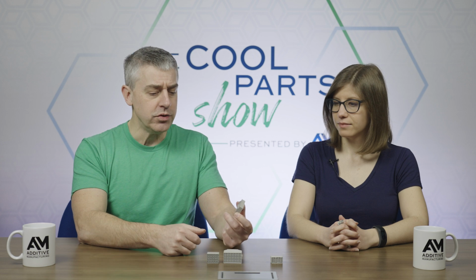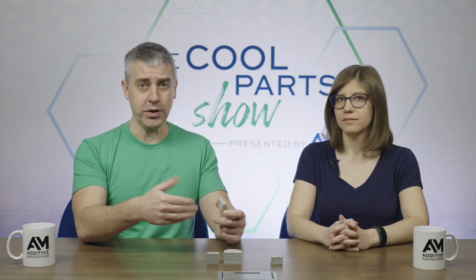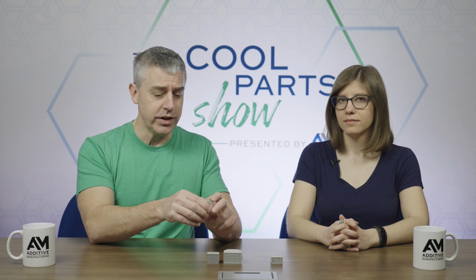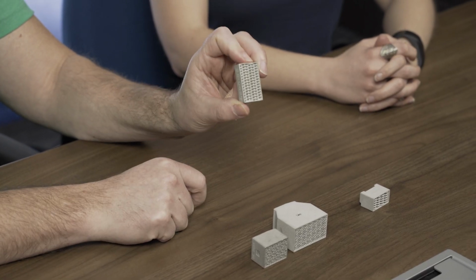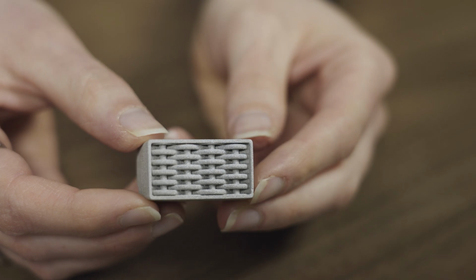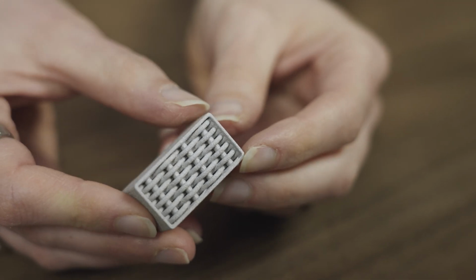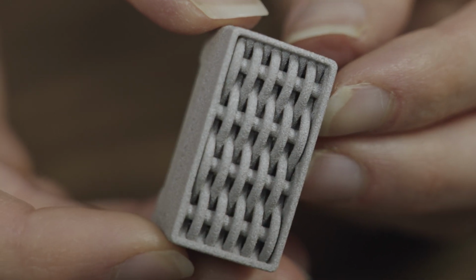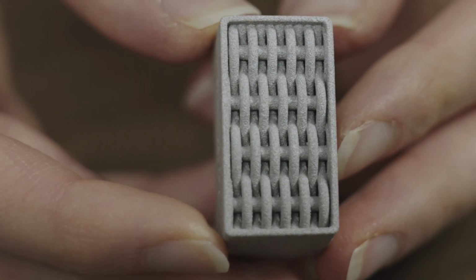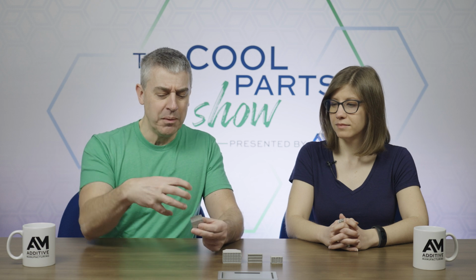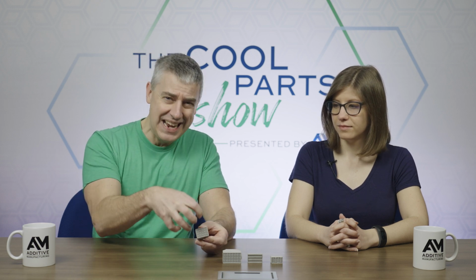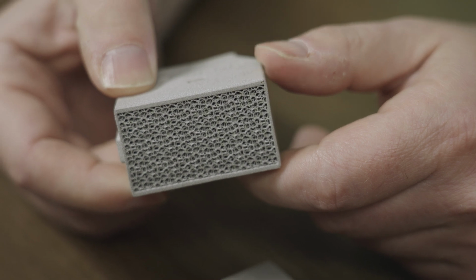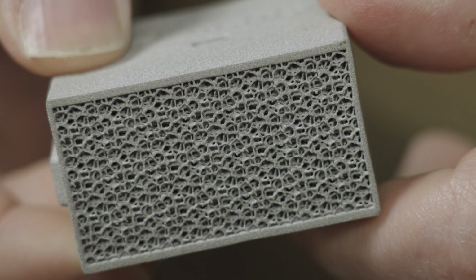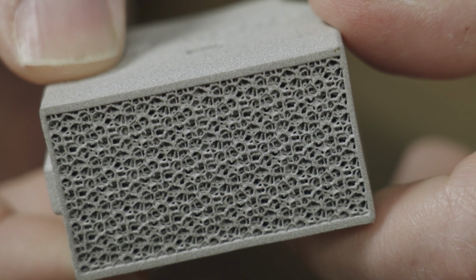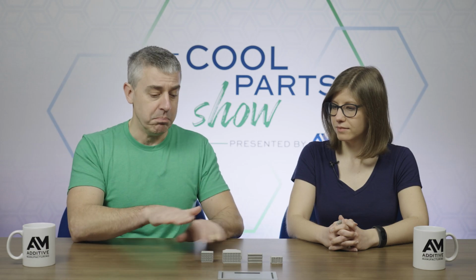But they're also reducing the pressure and the temperature of that gas. There's this basket weave texture, and that geometry is very good at reducing pressure by taking the gas flow and dividing it into a lot of parallel streams. Then there is also this more intricate, more elaborate, denser mesh. This part of the geometry has a lot of surface area, and it's very good at reducing the gas's temperature. Every breaker has multiple filters like this, both upstream and downstream.